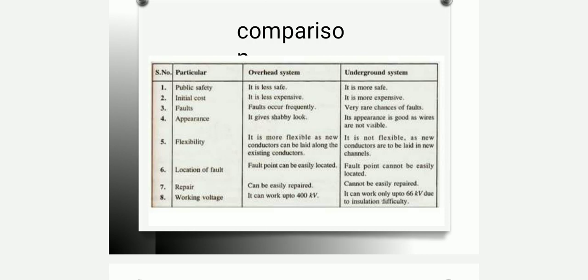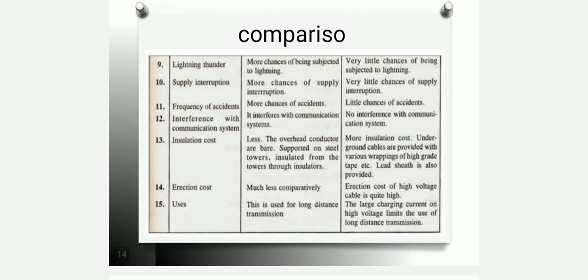For appearance, overhead lines give a shabby look whereas underground looks good because the cables cannot be seen. The flexibility of the overhead system is very high compared to the underground system, where cables are laid in fixed channels. Fault location is easy in overhead systems but cannot be easily detected in underground systems. Repair is easy in overhead but not easy in underground. For working voltage level, overhead can work up to 400 kV while underground can work only up to 66 kV due to insulation difficulties. Other differences include lightning, thunder, supply interruption, frequency of accidents, interference with communication systems, insulation cost, and erection cost.